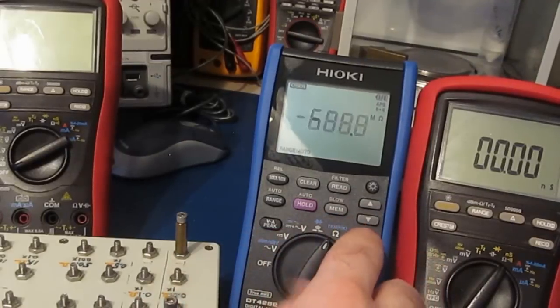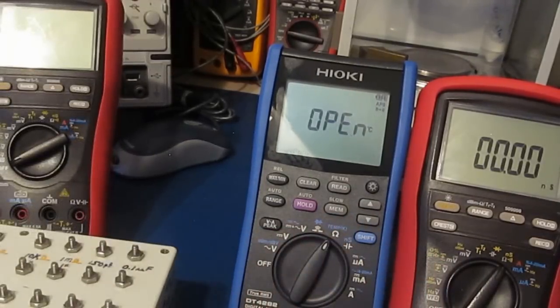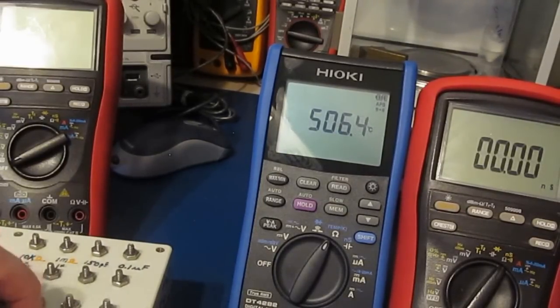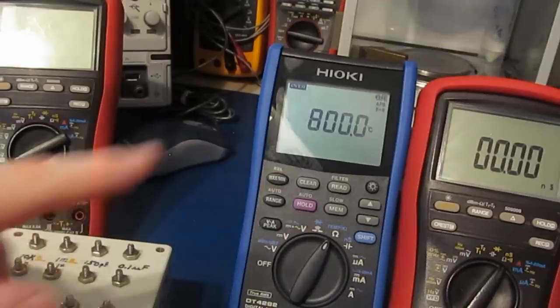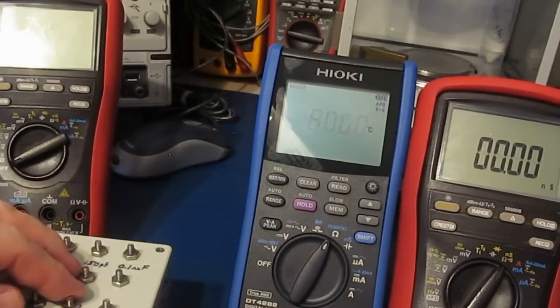Alright, let's try temperature. This should read roughly 500 degrees Celsius—that looks good. And again, this should be roughly 24 degrees C—that looks good. And this will be 1040 degrees C. Oh, looks like it can't read up that high, so 800 degrees Celsius is the maximum.